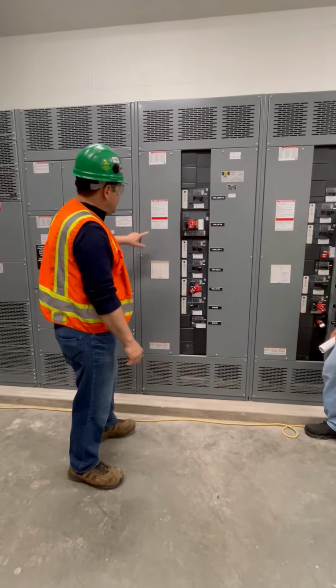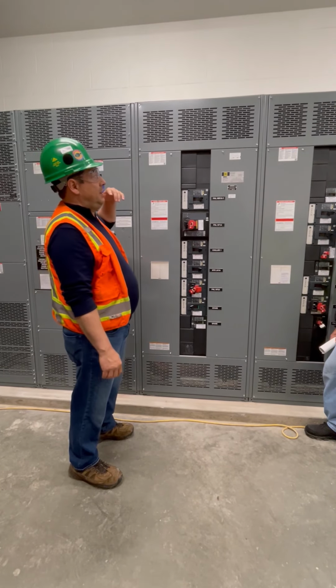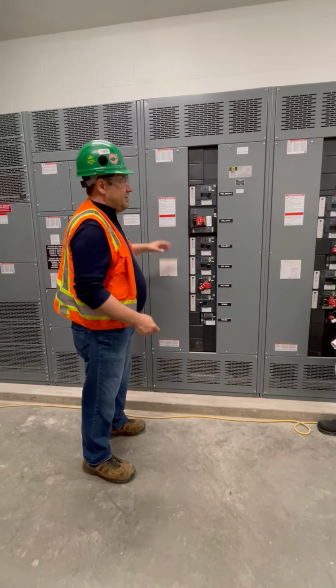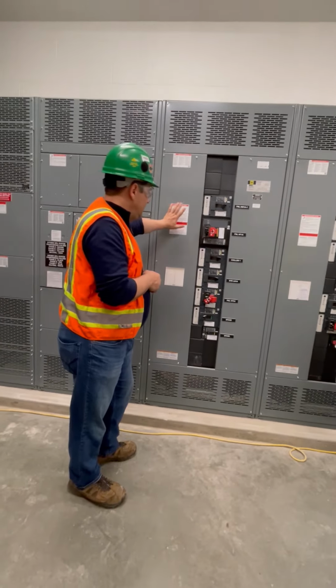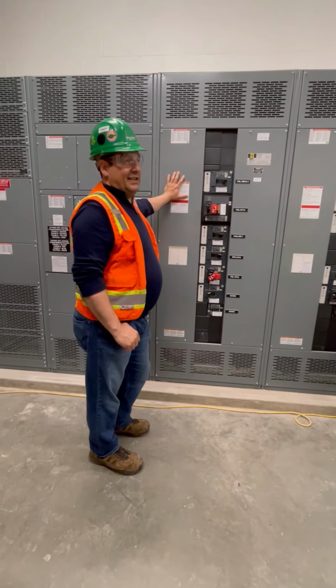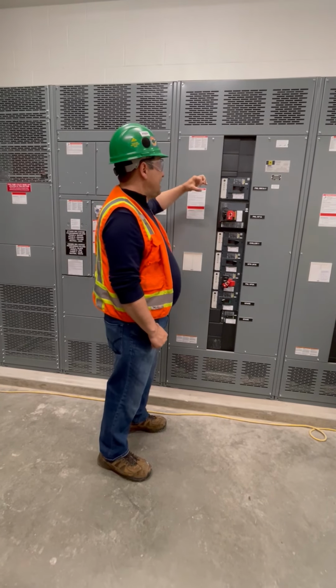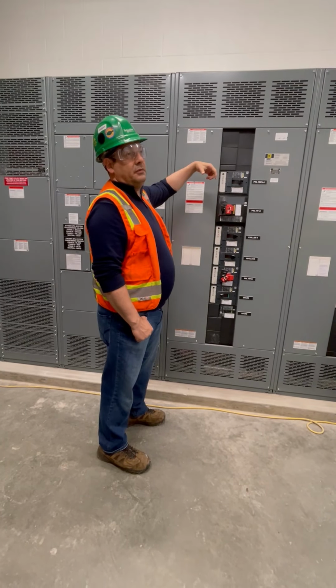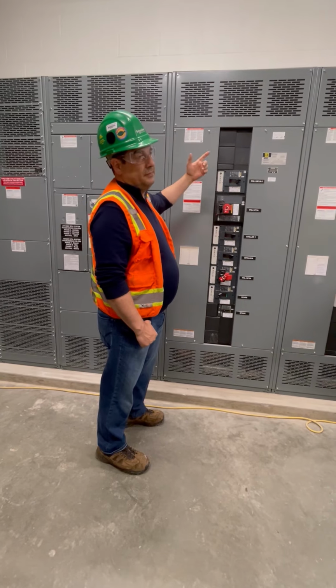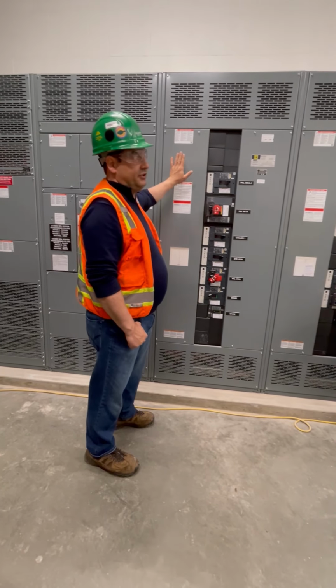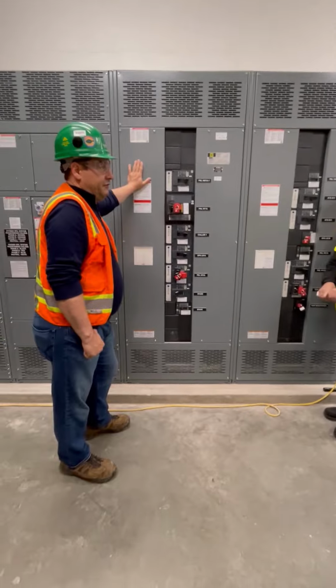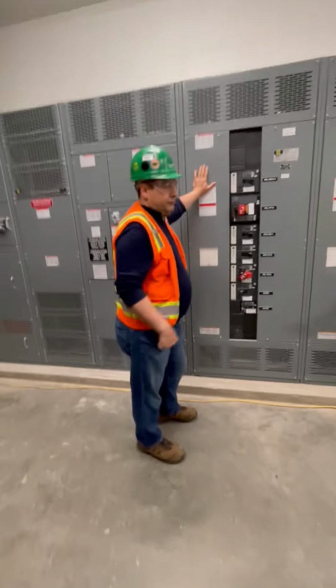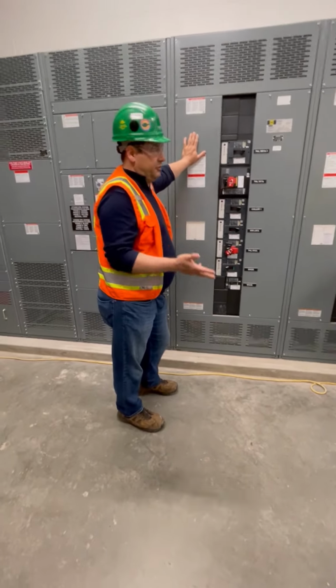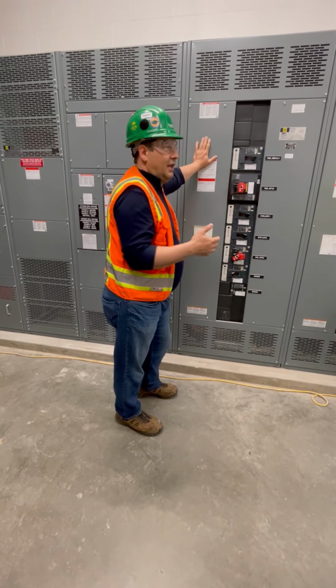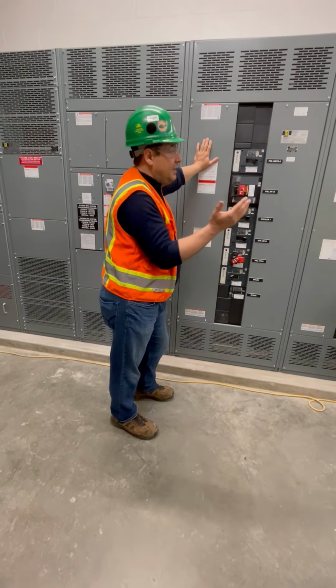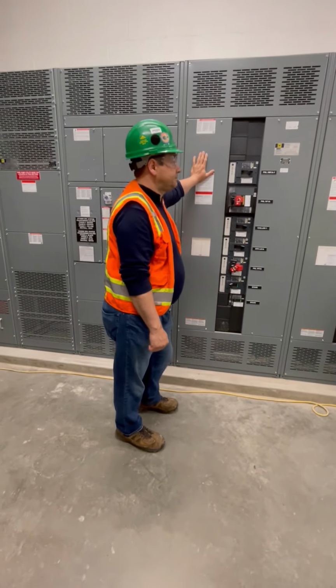Now, because of these kinds of incident levels, I'm going to go a little bit into the maintenance procedure, something that helps. In addition to these covers, we also have what we call the asset advisor. We can put heat sensors on the connections you can't get to, and they give you 24-hour information on those connections, right? So there are different things. If you need support on setting up maintenance cycles, what to do in maintenance, or some of the things that can help you maintain a switchboard, like infrared programs, let us know. We can work with you on that.